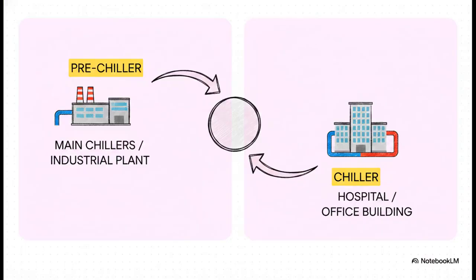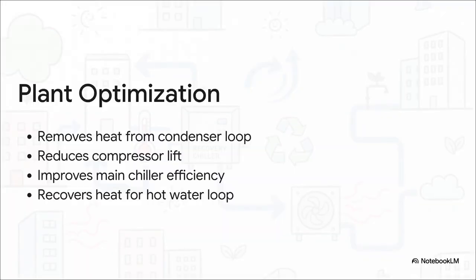Okay, so now that we know what it is, how do we actually apply it in the real world? There are 2 primary engineering designs used to capture this energy. Application 1 is central plant optimization, where the system is used to pre-cool the condenser water feeding your main chillers. Application 2 is direct production, where the chiller is directly responsible for producing chilled water and useful hot water for specific building loads. Let's break down exactly how both of these work. Starting with central plant optimization, you can think of this application as the ultimate team player for a massive facility. Imagine a large central plant with several standard water-cooled chillers.